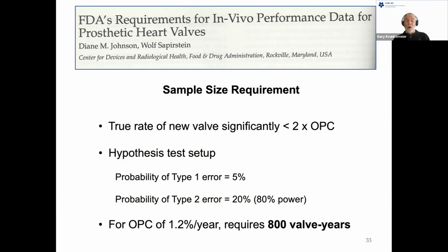And the sample size requirement based on that hypothesis test setup that the Gersh paper recommended showed that in order to prove this, they picked out one OPC, not the smallest, but kind of an average one, of 1.2% per year. And in order for a valve performing at that rate to prove statistically that it's less than 2.4%—double the OPC—it would require 800 valve years. So that was another condition that FDA used.